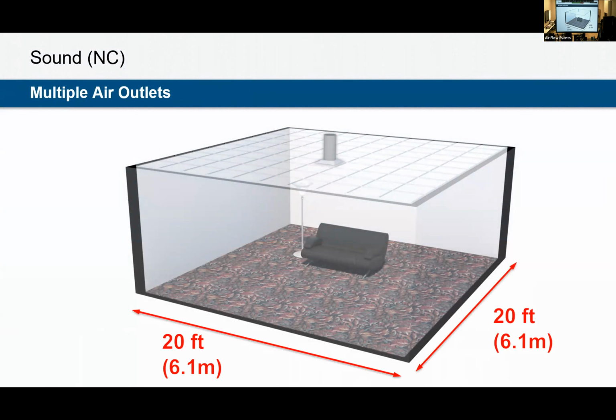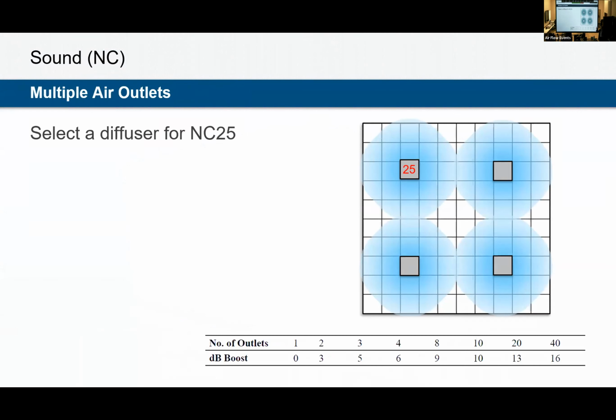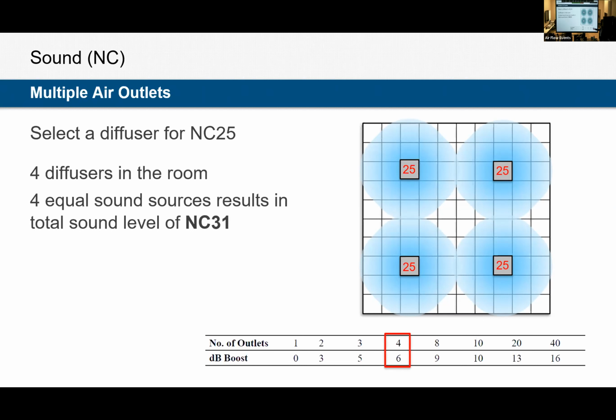So all those diffusers are cataloged assuming one diffuser in the space. We very rarely have one diffuser in the ceiling, and we're also assuming a room of this size, 20 feet by 20 feet. What happens if we have 4 diffusers? What actually happens to that sound? Per catalog, let's say one diffuser has NC 25. The result of adding 3 other diffusers with NC 25, so 4 total at NC 25, is that they're not additive. We don't now have NC 100 in the space. We're going to use this rule down here: if we've got multiple air outlets at the same NC level, we are adding only a small boost to the sound. So our one diffuser at 25 is now 4 diffusers at NC 31. NC is logarithmic, so it's definitely not sound source A plus sound source B equals C. It's a little more complicated than that.